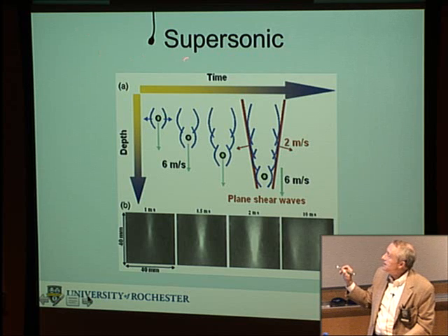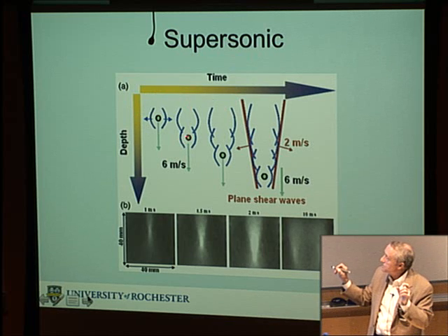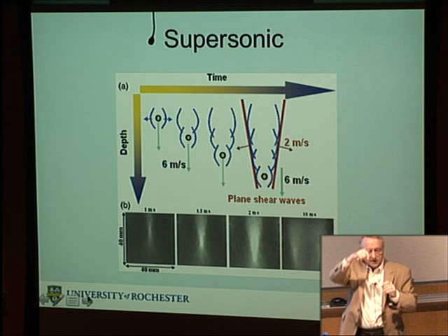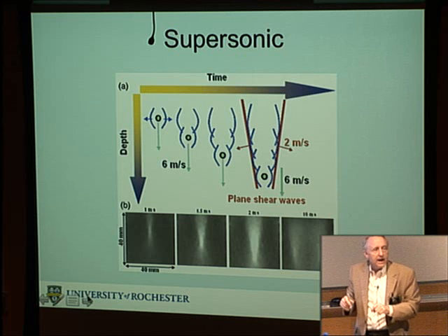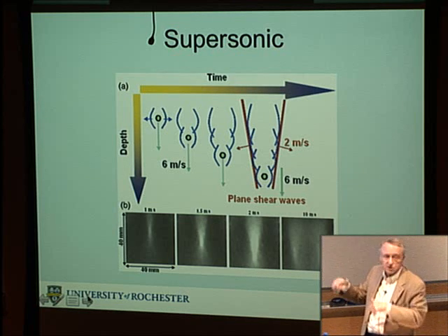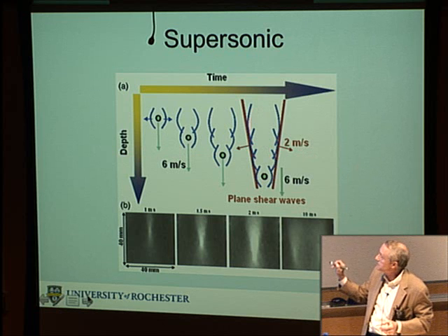And in fact, they can put a radiation force ping here, and then refocus, put another radiation force ping just a little below it, below it, below it. And so what I've done is I've put my radiation force almost in a line, and I have all the time in the world then to switch over to tracking mode and then track what now has become this line of shear wave traveling to the right, to the left, with a slight tilt because there's a little time delay.